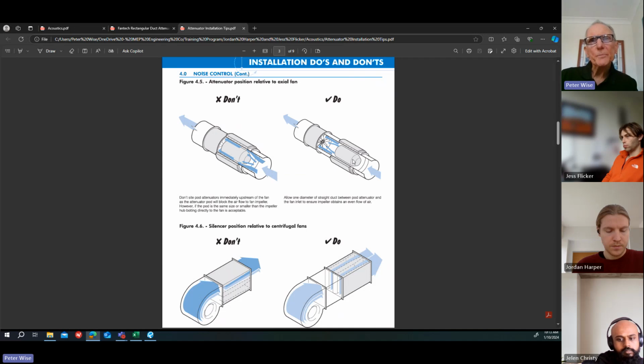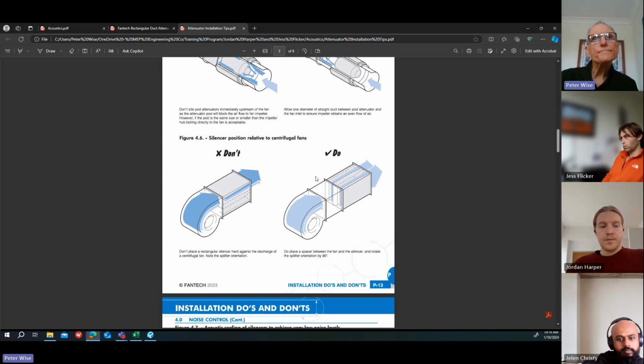What you can do if you have a podded attenuator is ask the attenuator suppliers to provide that extra piece of duct to attach to the fan, because if it's Fantech, for instance, they will supply the attenuators and the fans. So you can just ask them to make the attenuator longer. So finish the pod, say, 1 metre before the fan and increase the casing up to the fan. They can make all that for you, which makes it easier.